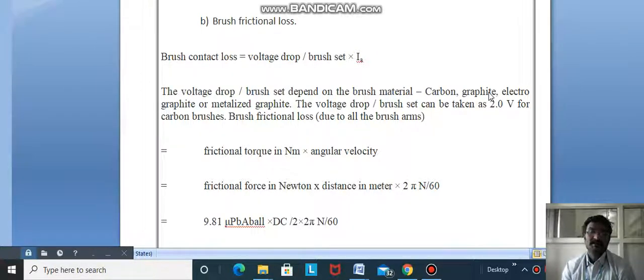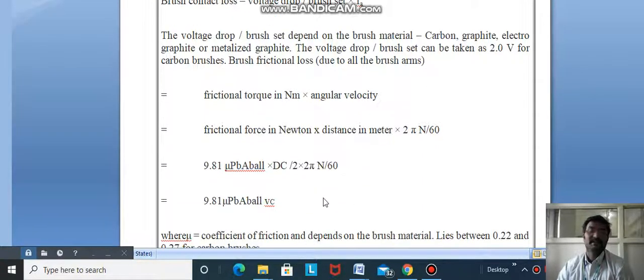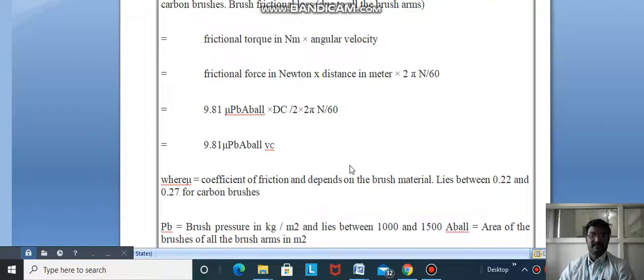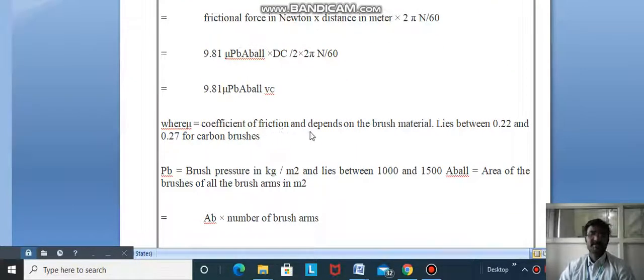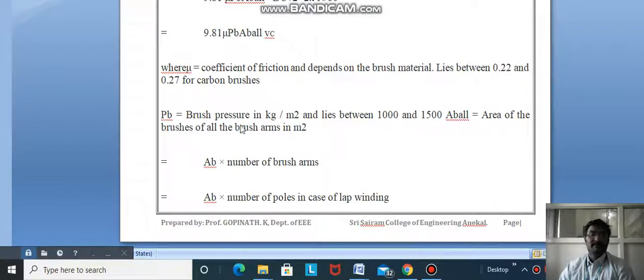The voltage drop per brush set can be taken as 2.0 volt for carbon brushes. Brush frictional loss equals frictional torque in newton meter multiplied by angular velocity, which equals friction force in newtons multiplied by distance in meters times 2π N/60. This equals 9.81 μ Pb Ab times Dc/2 times 2π N/60, where μ is the coefficient of friction.